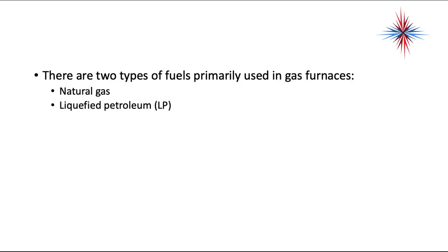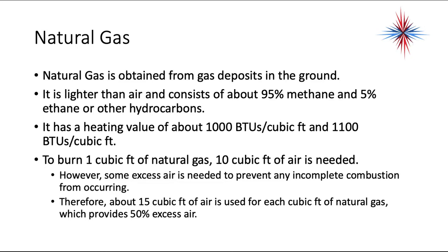There are two types of fuels primarily used in gas furnaces: natural gas and liquefied petroleum. Natural gas is obtained from gas deposits in the ground. It's lighter than air and consists of about 95% methane and 5% ethane and other hydrocarbons. It has a heating value of about 1,000 to 1,100 BTUs per cubic foot. To burn one cubic foot of natural gas, 10 cubic feet of air is needed. However, some excess air is needed to prevent incomplete combustion, so 15 cubic feet of air is used per cubic foot of natural gas — providing about 50% excess air. If you're taking a certification test, you absolutely must know: 10 cubic feet for complete combustion, 15 cubic feet under normal conditions.